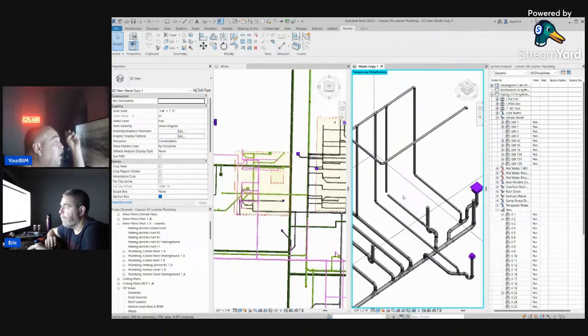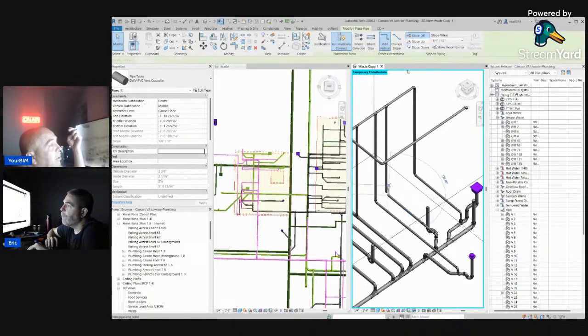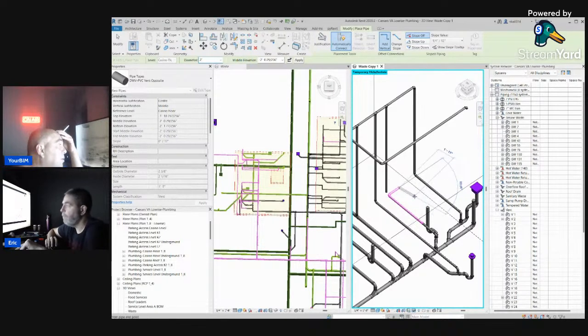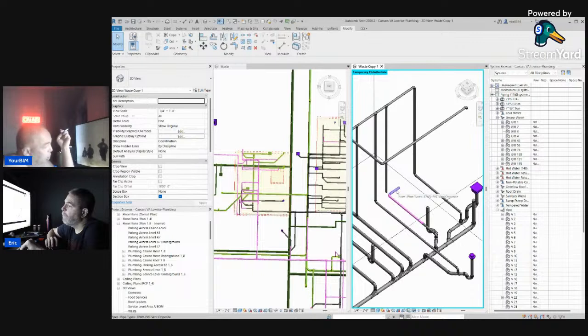Now, if you've done this correctly, if you pick that pipe and you go to the little blue dot on the end and you say draw pipe, it should automatically be drawing in the proper vent. So right click and say add pipe. And then draw a little bit, 90 degrees. Perfect. See what it did? Okay. That's because that system was charged with that control from that fitting that I created.